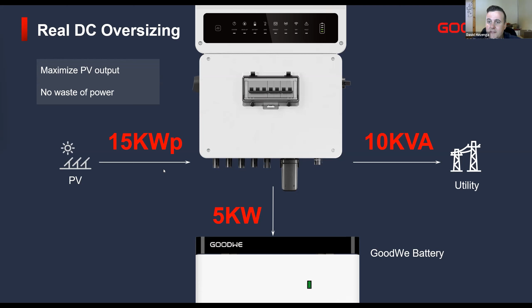So if you do have a customer who has a high AC demand, even if it's on the utility side, you can oversize that PV. It can still match that 10 kilowatt demand during the day, as well as still charge your batteries at a rate of up to 5 kilowatts, to make sure that the batteries get full by the night time to compensate the loads during the night. So that's great for customers who have big daytime loads and to really maximize the system and the benefits. And I'm sure Renier is going to explain quite a bit how this can work very well with load management.